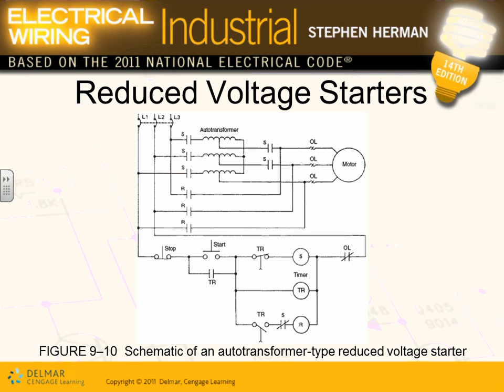Any comment, guys, about voltage reduction? The only thing I want you to understand is, when you go to commissioning and they ask you what the controller on this motor is, they're going to be talking about voltage reduction. Here's the voltage reduction. You take 480 to a transformer, you reduce it to 240, start your motor for only 10 seconds. After 10 seconds, you shunt the transformer out and the system is running at 480. Any comments, any questions, guys, about this auto transformer? Aaron, does it make sense?